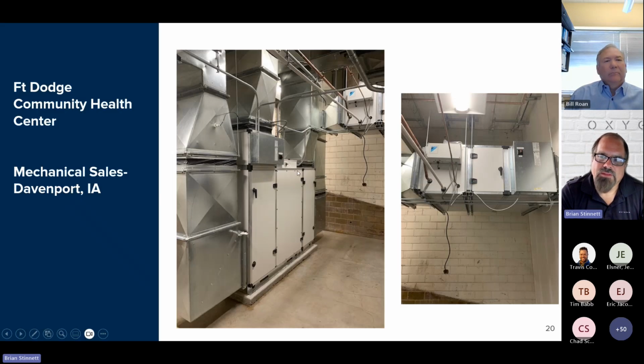Here's an example. They flip the energy recovery unit up on its edge, brought the supply duct up, turned 90 degrees, and then here's a VRV heating cooling coil, an access section, and then an SCR electric heater as post heating for dehumidification in the summer, also as backup heating in the wintertime. Now, this project was in Iowa at the Fort Dodge Community Health Center, extremely cold winter conditions, and they wanted backup heating in case anything went wrong with the DX system.